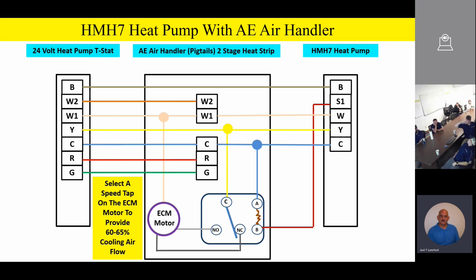When the outdoor unit comes down to a point of modulation of about 60%, it's going to generate an S1 signal. It's going to energize that relay, and it's going to switch that motor to a lower speed tap. Because remember, when we reduce the capacity of the outdoor unit, we also want to reduce the airflow inside to give you the best we can for humidity control as well as comfort. So that's the whole idea of this relay: to reduce the airflow when the outdoor unit reaches a point of capacity where it wants reduced airflow for comfort and humidity control.